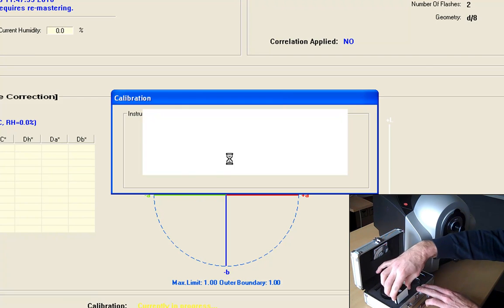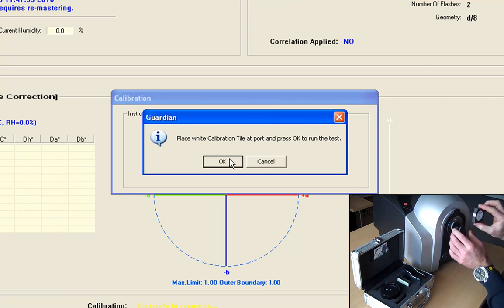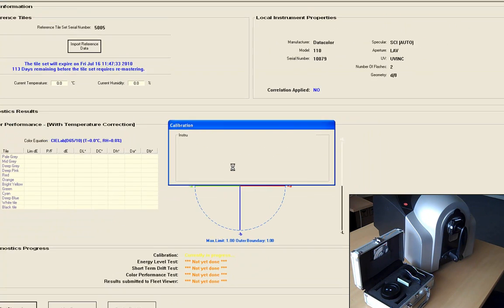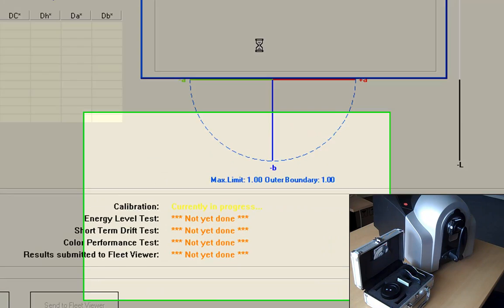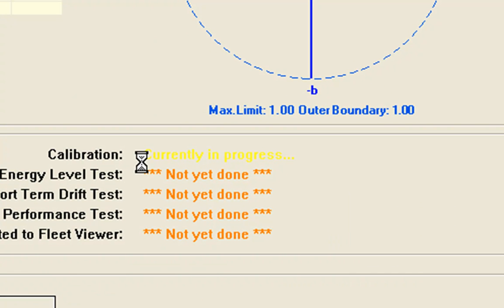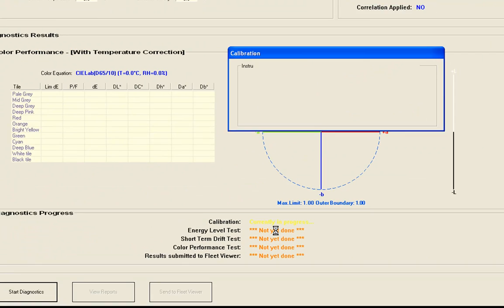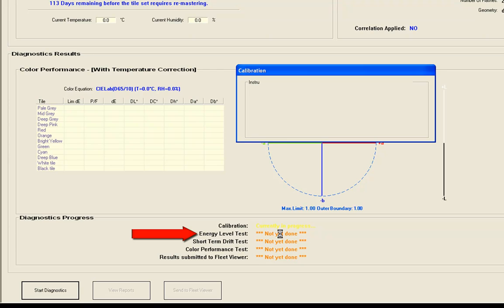So black calibration is done, and now the white calibration tile is asked to present. So we click OK. You see here calibration currently in progress. The next step will be the energy level test, and this test will be done automatically on the white tile. This test is measuring the internal levels of the monochromator. It automatically checks fibers, lenses and electronics.